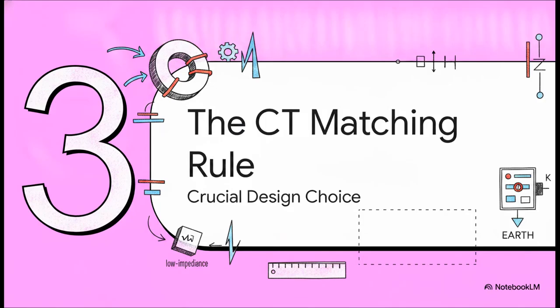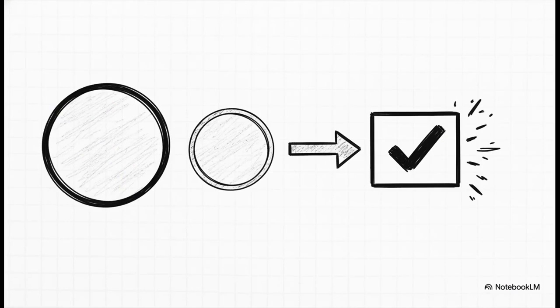Which brings us nicely to Section 3, the CT matching rule. This is the unbreakable engineering rule that makes your decision for you. Mismatched CTs completely require low impedance REF. Let's say you're doing a brownfield retrofit. Your phase CTs are 2000/1, but your old legacy neutral CT is 1000/1. Guess what? You are automatically locked into the low impedance scheme. High impedance is off the table right then and there.